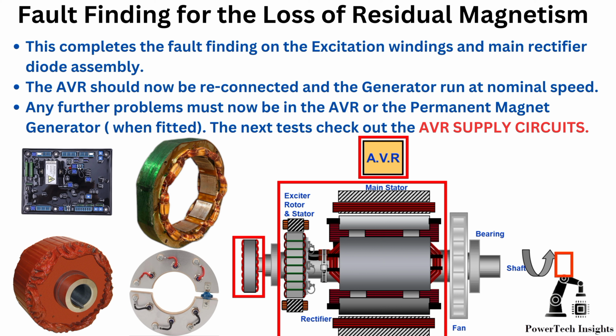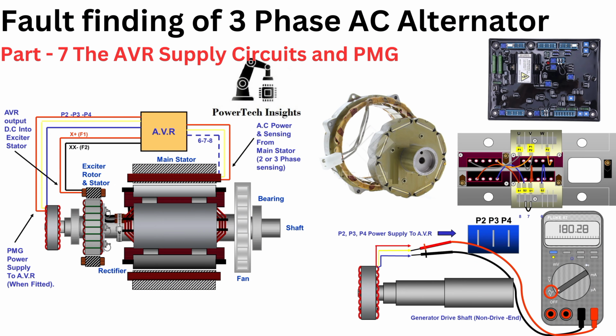The AVR should now be reconnected and the generator run at nominal speed. Any further problems must now be in the AVR, or the permanent magnet generator if fitted. The next test, check out the AVR supply circuits. Part 7, the AVR supply circuits and PMG.